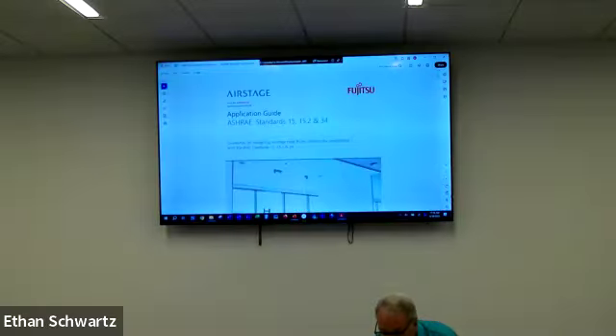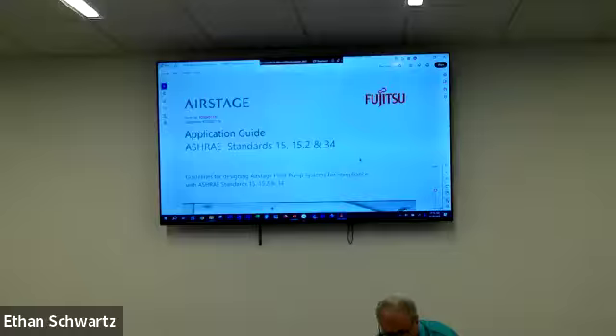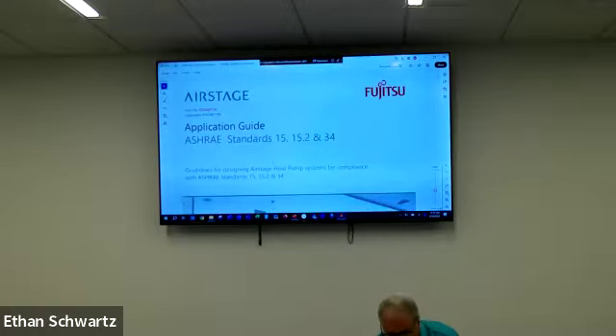We have this application, and if anyone would like this, this is the full ASHRAE standards 15 and 15.2, because it wasn't until the A2Ls came in that they made a second one specific for residential, because R410A pretty much hit everything residential. And then also ASHRAE standard 34.